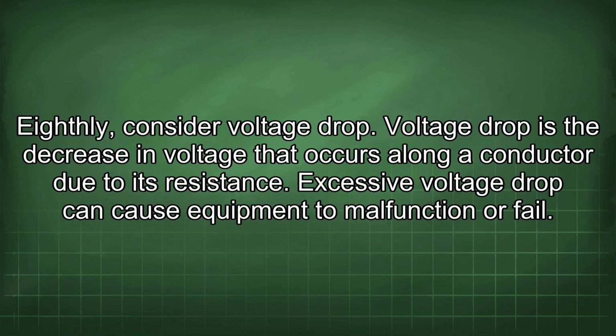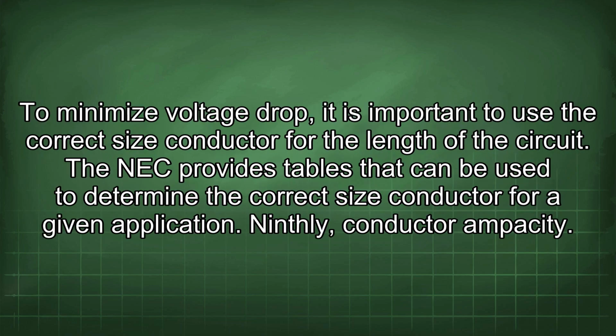Eighthly, consider voltage drop. Voltage drop is a decrease in voltage that occurs along a conductor due to its resistance. Excessive voltage drop can cause equipment to malfunction or fail. To minimize voltage drop, it is important to use the correct size conductor for the length of the circuit. The NEC provides tables that can be used to determine the correct size conductor for a given application.